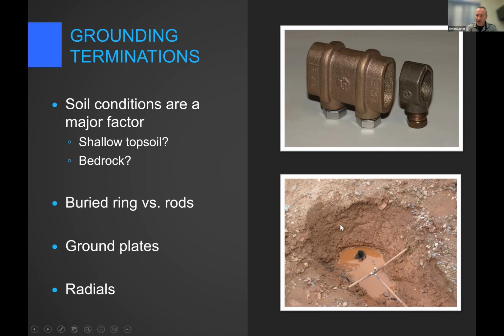Yes, we can do, that's only for a clamped connection. We can still do exothermic welding. You can still do high press grounding. That's also okay for lightning. But if you're using a bolted fitting, it has to be bigger. It has to be more substantial. It has to be listed for the purpose. Once again, back to the UL, you see the UL stamp on the lightning fitting there. It is listed for the purpose of lightning protection. And there is a standard that applies to the manufacturers of those.